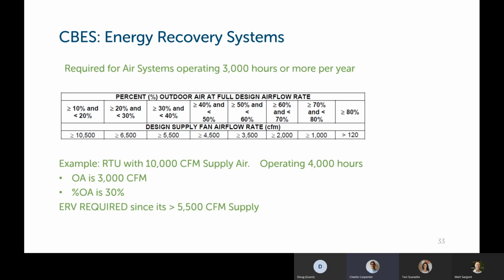So I copied and pasted the table in the middle there from the code. And what's important to note here is that energy recovery is required for air systems that are operating 3,000 hours or more per year. If that's the case, then you would look at this table to try to see whether or not you need to put it in with the code. And it's a little complicated looking through this. Even I look at it all the time and I still get confused with it.